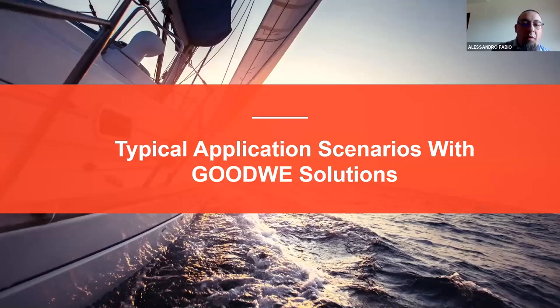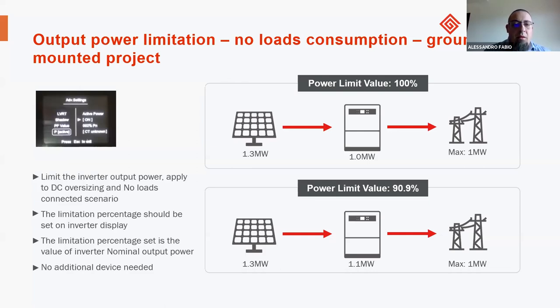So we spoke about the typical application scenarios with the GoodWe solution. You have the possibility, for example, as I spoke about self-consumption, or in this case power limitation. In the case that no load consumption or self-consumption is needed and the system is ground-mounted, you can limit the power directly on the display. This is the standard solution. You can choose this directly on the display or through the app, setting the power limit function on site for each inverter.